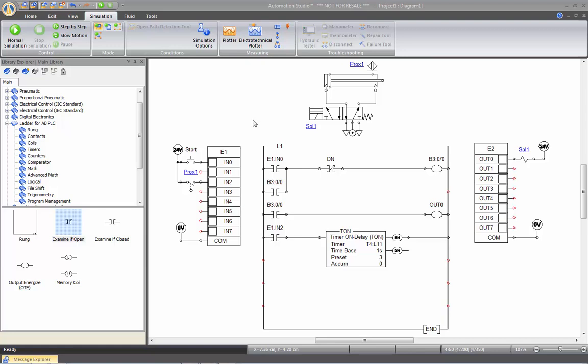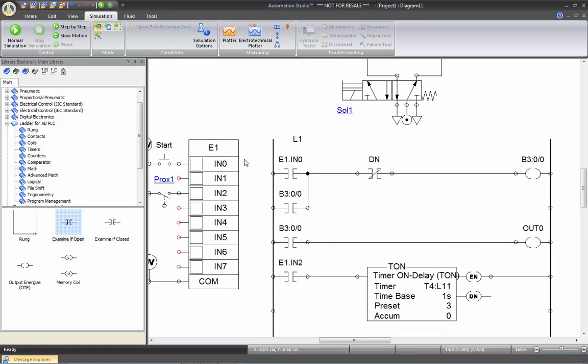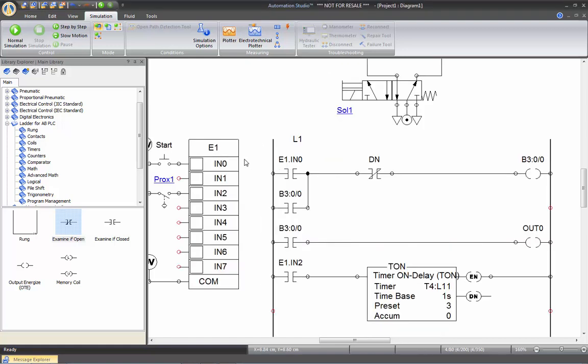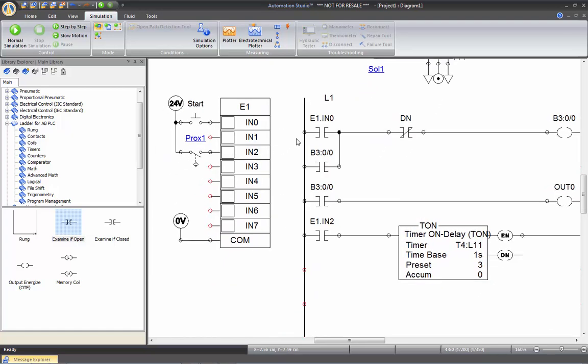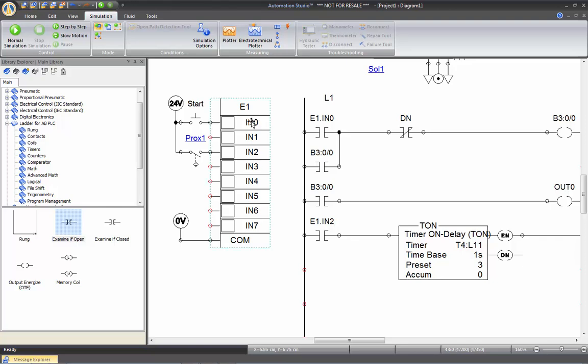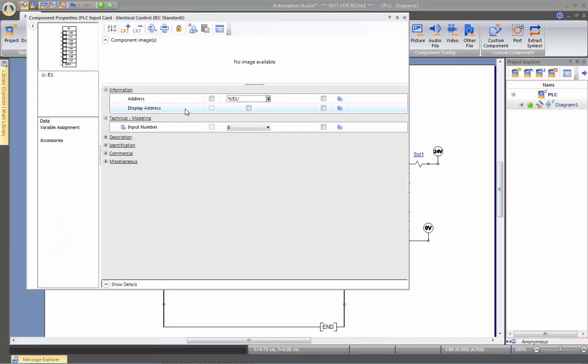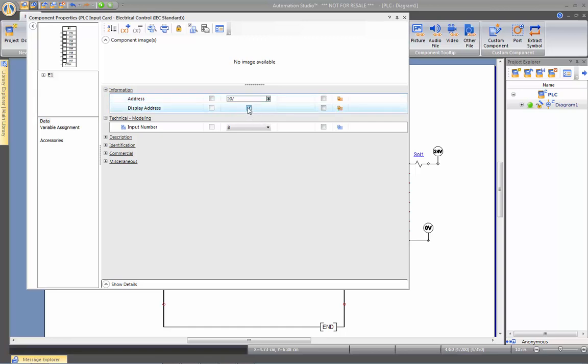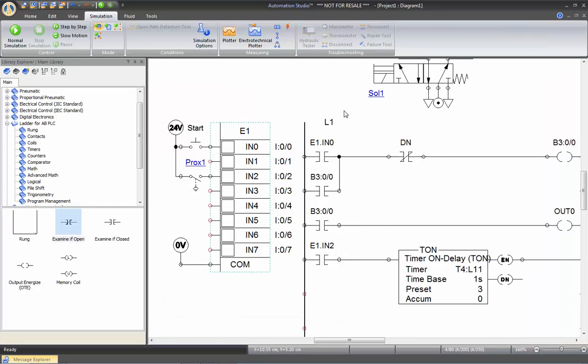Another feature which you can also do in the PLC library is actually change the way you want to display the internal ID or addresses on your contact. Let's zoom in this section a bit. So you see right now my contact shows E1 dot IN0. But let's say you want to show the addresses of your PLC. And from here in the address, you can change the way it is displayed. So for example, let's put I colon zero slash and then the input. And if you check this box, you will actually display on your drawing the addresses. So if you close this window now, you'll see that you have all the addresses.